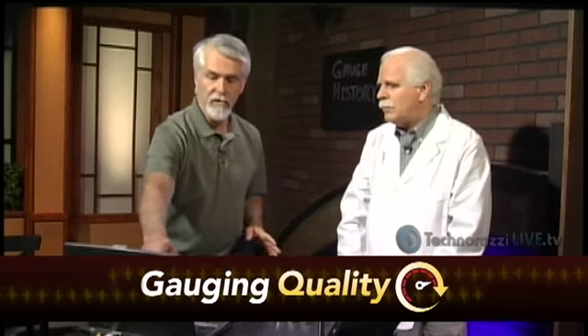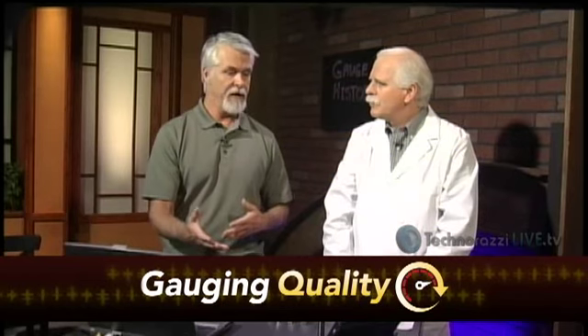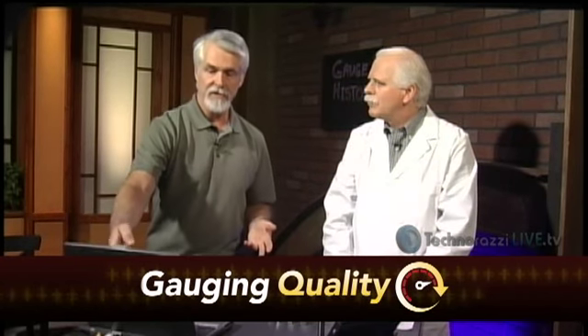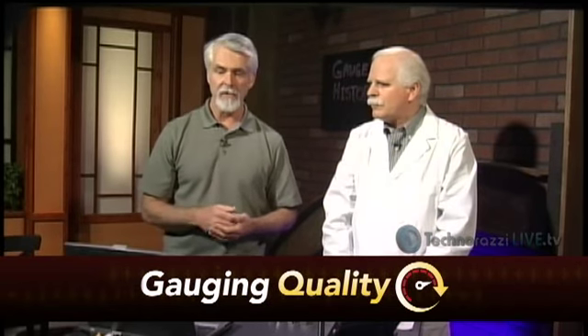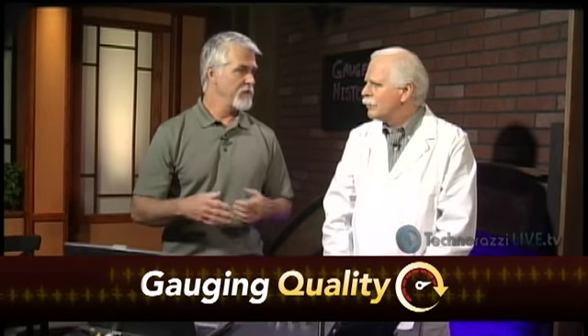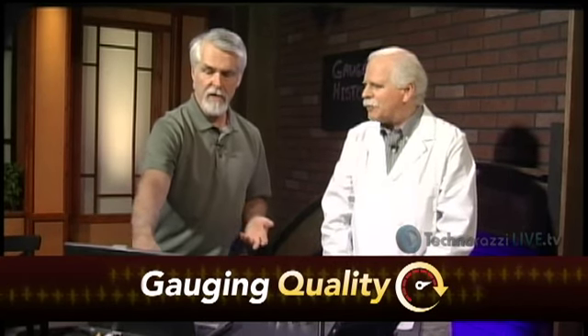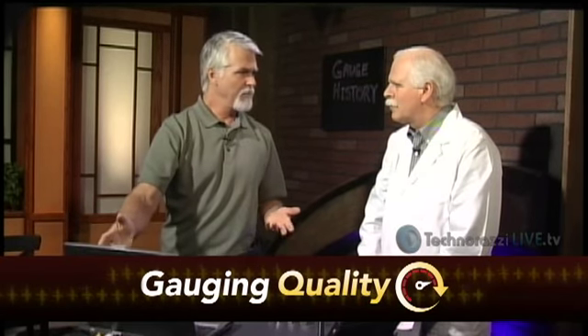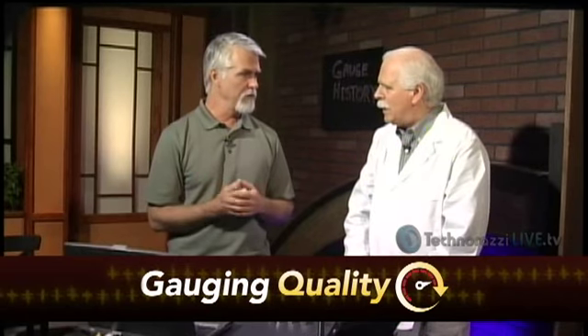So if you were looking at this, if you were just somebody who came in new to the calibration lab, and you got this gauge pin, and you measured it, and you saw it's a little on the low side, but it passes, that would be the last you would think of it. But if you actually had seen the trend, you would go, geez, this is going down pretty steep. If it continues this trend, by next year this gauge plug could very well be out. It may be out, okay.